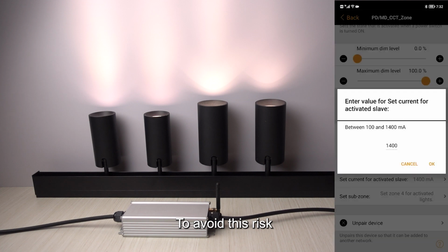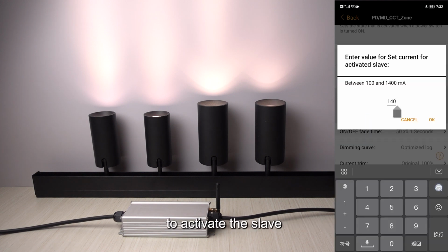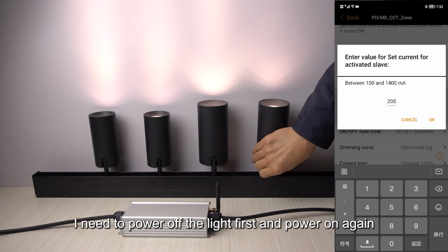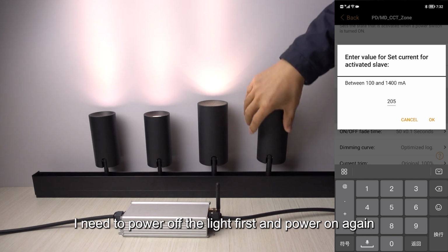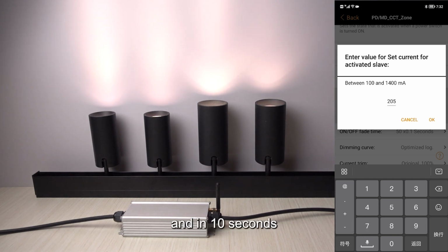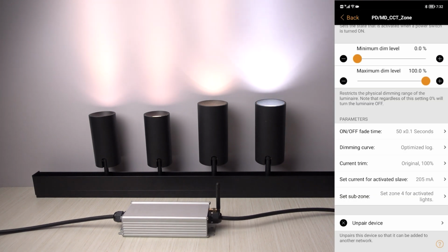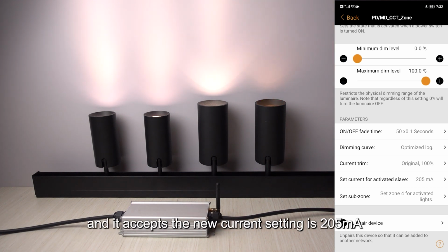And to avoid this risk, you must activate the slave first. To activate the slave, the operation is the same as the zone feature. For example, I go to a lower current. If I want to write this current to the light, I need to power off the light first and power on again. And within 10 seconds, input the current and press OK. Now this light is activated and it accepts the new current setting of 205 milliamp.